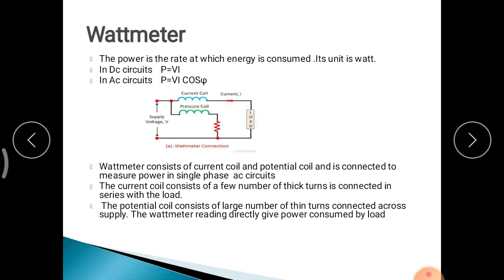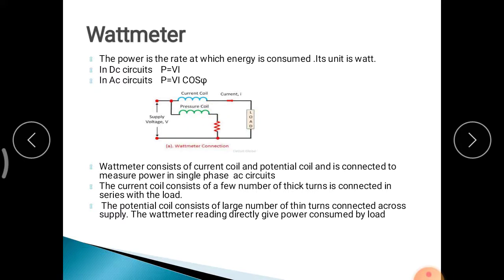In the Watt Meter connection diagram, there is a current coil and a pressure coil. The current coil is connected in series with the load, and the pressure coil is connected in parallel or across the supply. The current coil consists of a few thick turns of wire connected in series with the load, and the pressure coil consists of a large number of thin wires connected across the supply. The Watt Meter reading directly gives the power consumed by the load.